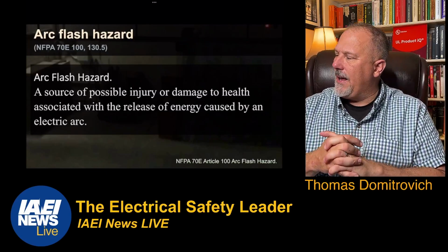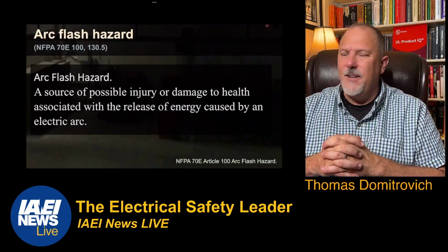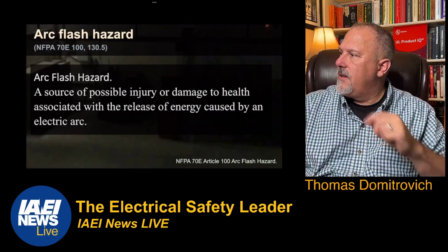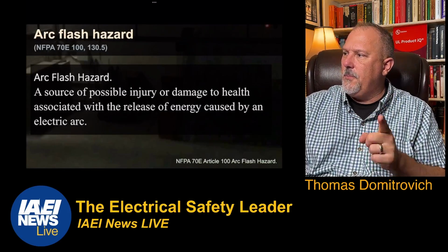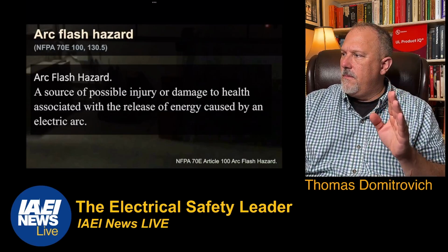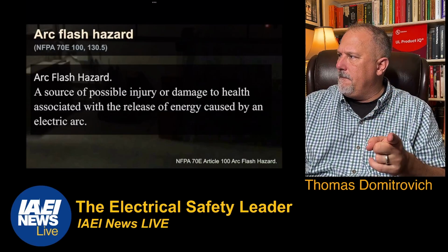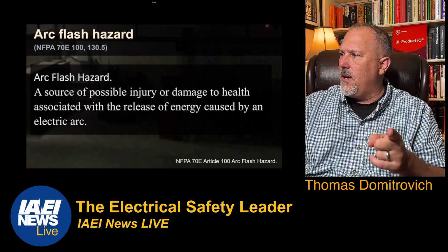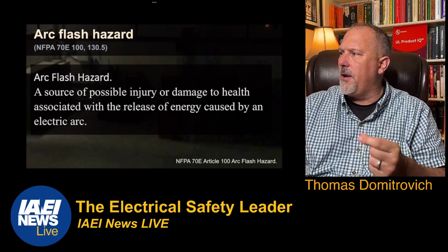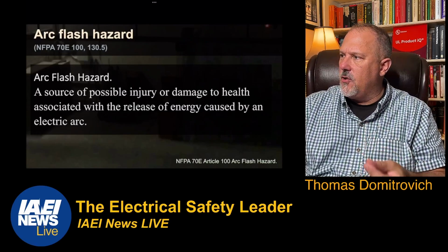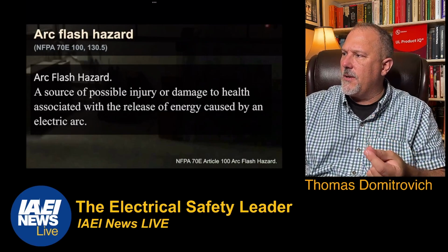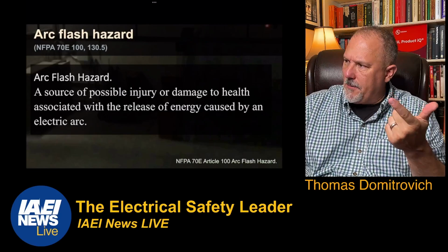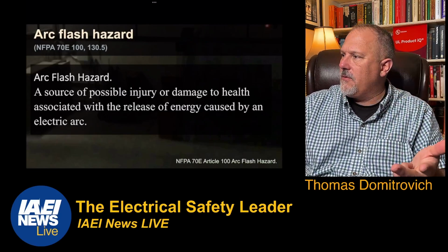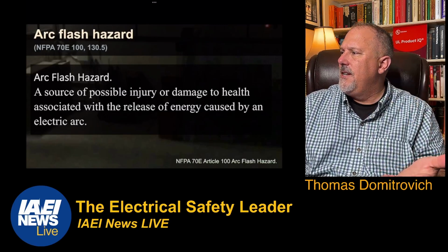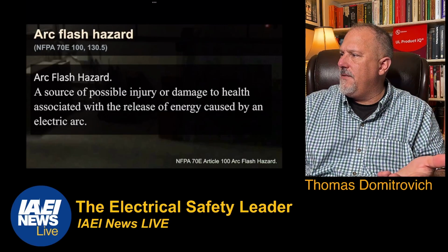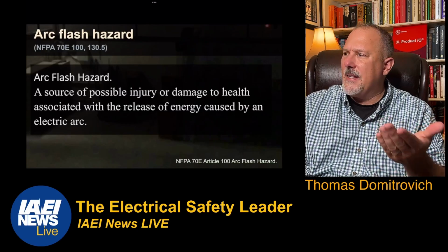And speaking to that, they have an informational note reference to 110.2(B). 110.2(B) has an exception 1, which is normal operation of electric equipment shall be permitted where a normal operating condition exists. A normal operating condition exists when all the following are satisfied. The equipment is properly installed, the equipment is properly maintained, the equipment is rated for the available fault current, the equipment doors are closed, all equipment covers. So that is exception number 1.